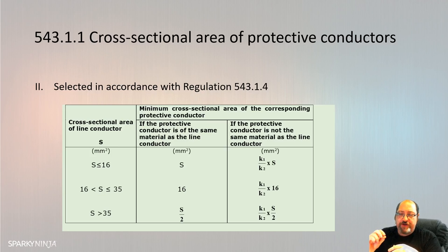Back boxes have an earth terminal because if you use the wiring system, a glanded armoured or a steel conduit, if you're using the wiring system as your main protective conductor route and not a CPC within the system, then you need to find a way to take that wiring system and bring it to the accessory. Yeah, and that's what that is saying.